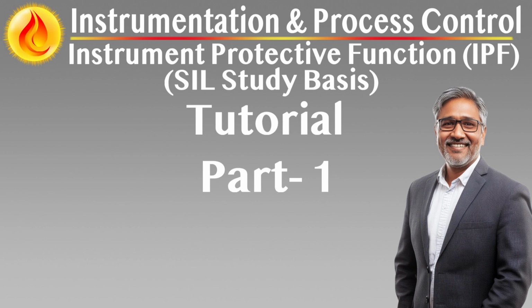The IPF must be designed and verified to meet or exceed the assigned performance level. This includes reliability modeling using tools like fault tree analysis, FTA, or failure modes and effects analysis, FMEA, selection of certified components with known failure rates, e.g. IEC 61508, 61511 compliant, evaluation of diagnostic coverage, test intervals, and safe failure fractions, documentation of assumptions, data sources, and calculation methods.